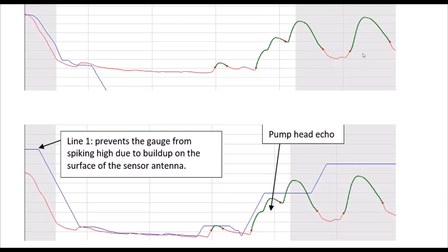echo. Now you don't see this problem every day because you have to hit a certain level in that lift station and it has to have a metal lid. Now if the lift station stays open at the top, you do not see this. But now if it has a metal lid and you close it, then you could potentially see this problem. Now, here is the easy setup that will fix it.